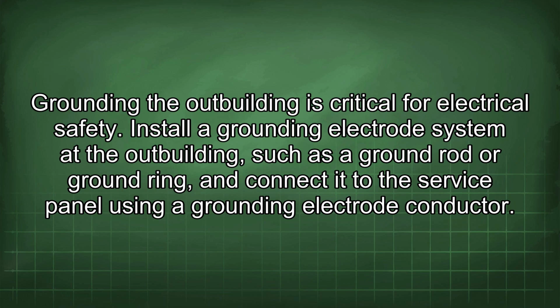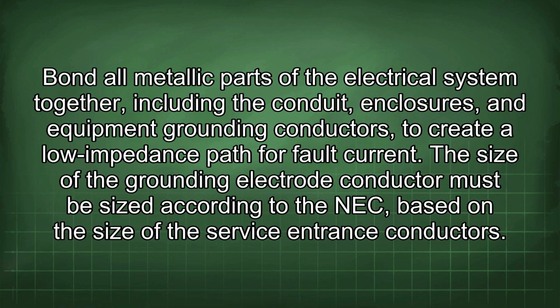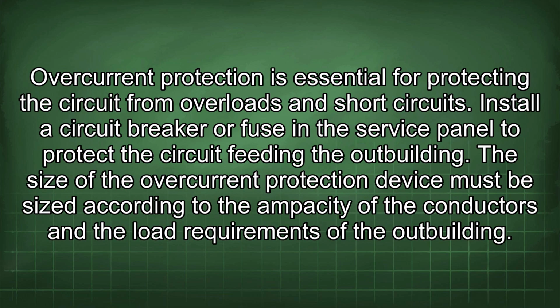Install a grounding electrode system at the outbuilding, such as a ground rod or ground ring, and connect it to the service panel using a grounding electrode conductor. Bond all metallic parts of the electrical system together, including the conduit, enclosures, and equipment grounding conductors, to create a low impedance path for fault current. The grounding electrode conductor must be sized according to the NEC, based on the size of the service entrance conductors. Overcurrent protection is essential for protecting the circuit from overloads and short circuits.